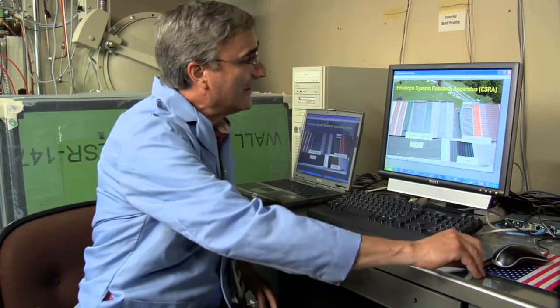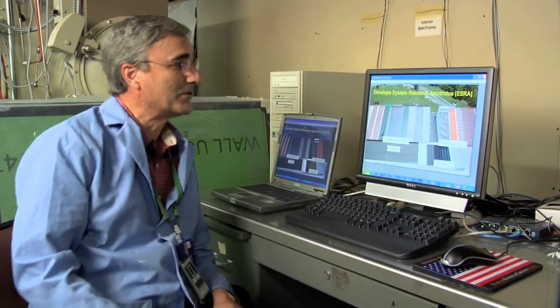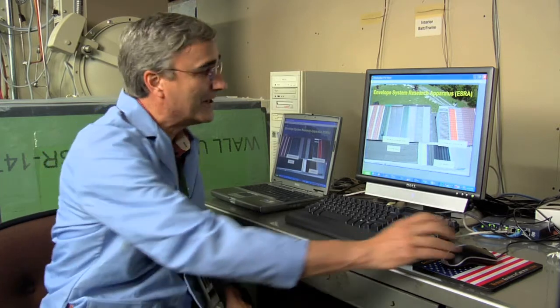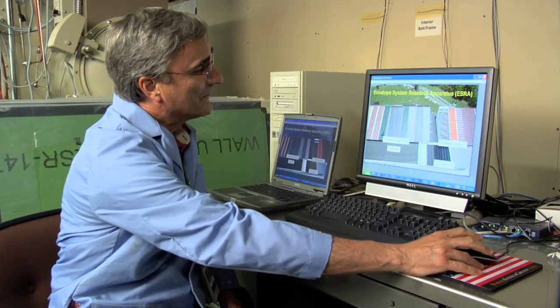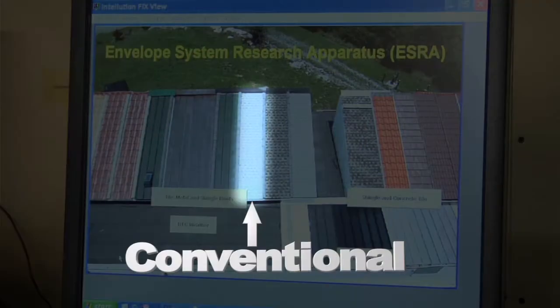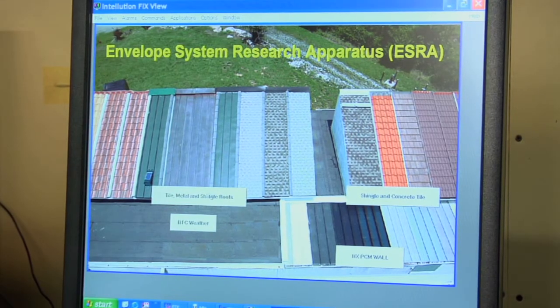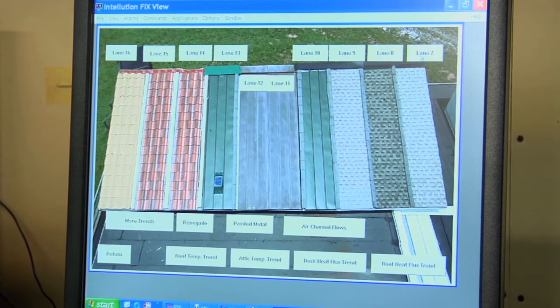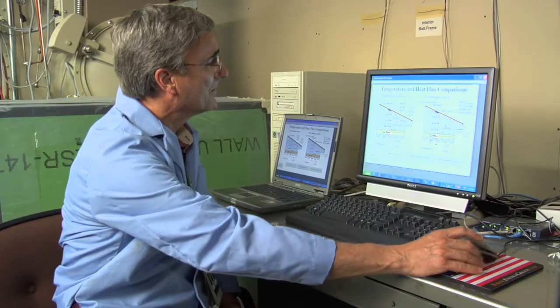We're inside the laboratory and this is my data acquisition center. I'm going to show you results for two different roof assemblies that we have under test. One is our control asphalt shingle that we compare all our roofing systems to. It's just a conventional, direct-nailed shingle roof with typical attic ventilation. Right next to it, I have a very unique roof system built by Billy Ellis Roofing. I'm going to compare the results of these two houses in terms of the actual heat flows through the roof deck and also the temperatures.